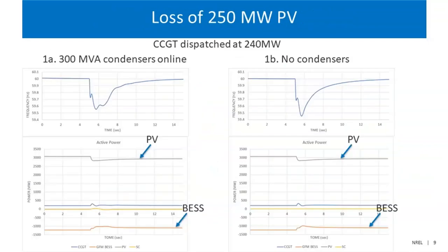So we did a number of simulations. Here is one use case where everything on the island is essentially PV and grid-forming storage. There is only one remaining combined cycle unit operating, and at that moment, we lose about 250 megawatts of PV, several very large PV plants in one part of the island. And these are two cases, where the 300 MVA synchronous condensers were distributed along the island and no condensers. So you can see that the system recovers okay at this very high penetration case. This is because of the grid forming battery systems. As far as the frequency response itself, there is very little gain in terms of nadir and the RoCoF. This is mainly because of the inertia of the synchronous condensers, but it's not very critical.